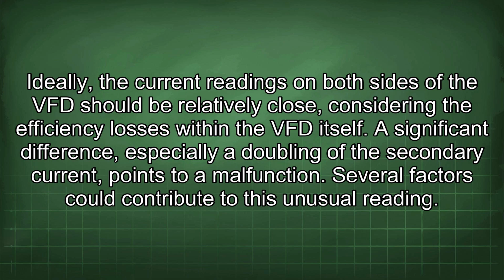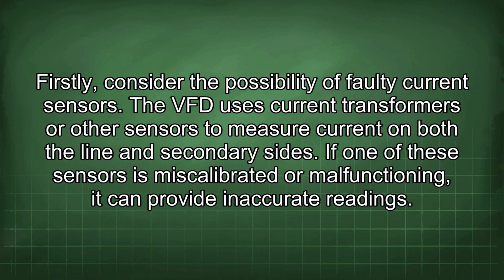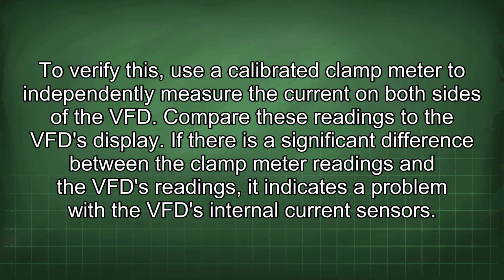Several factors could contribute to this unusual reading. Firstly, consider the possibility of faulty current sensors. The VFD uses current transformers or other sensors to measure current on both the line and secondary sides. If one of these sensors is miscalibrated or malfunctioning, it can provide inaccurate readings. To verify this, use a calibrated clamp meter to independently measure the current on both sides of the VFD. Compare these readings to the VFD display. If there is a significant difference between the clamp meter readings and the VFD readings, it indicates a problem with the VFD internal current sensors.